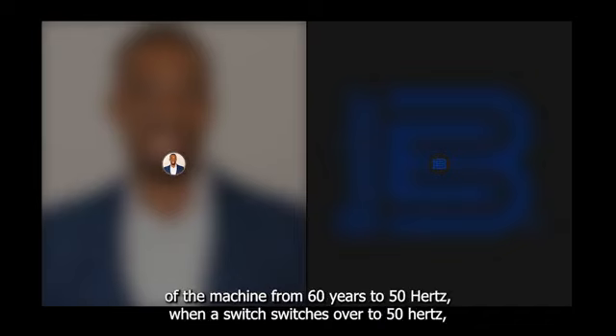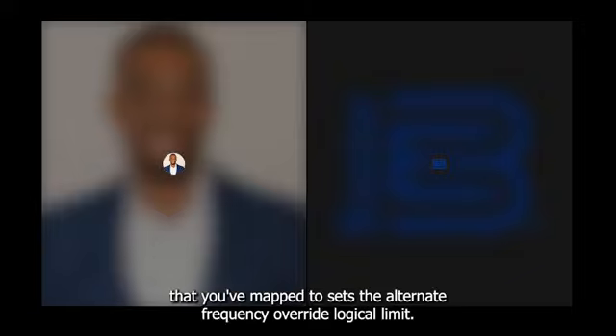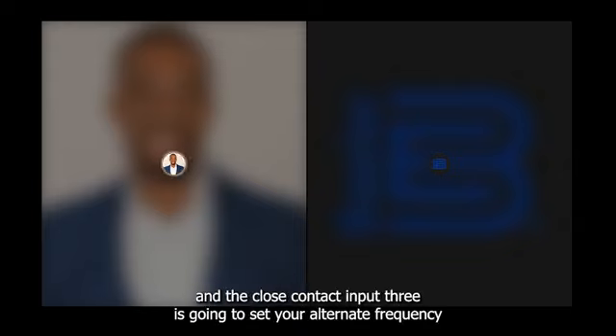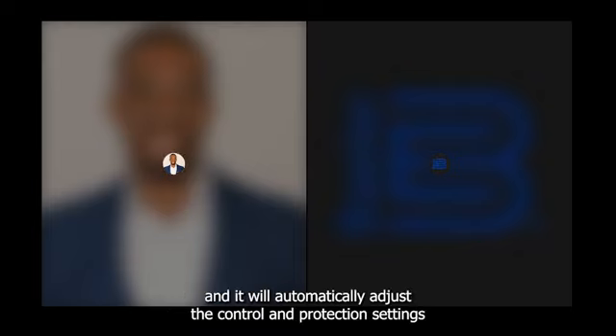If you're using a selector switch to change over the frequency selection of the machine from 60 hertz to 50 hertz, when that switch switches over to 50 hertz, then that switch position needs to close a contact that you've mapped to set the alternate frequency override logic element. Let's say you've chosen contact input 3. When your switch on your generator switches over to 50 hertz, that position needs to close contact input 3, and the closure of contact input 3 is going to set your alternate frequency override logic element. The controller will then determine that the machine is operating at 50 hertz, and it will automatically adjust the control and protection settings by the alternate frequency scale factor.